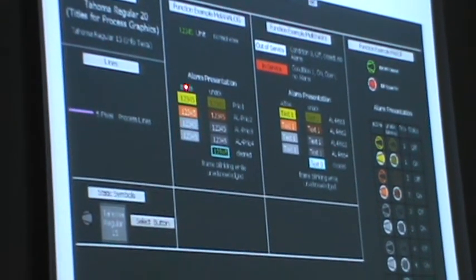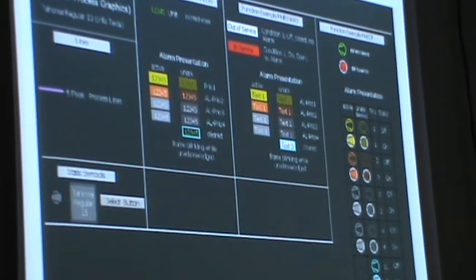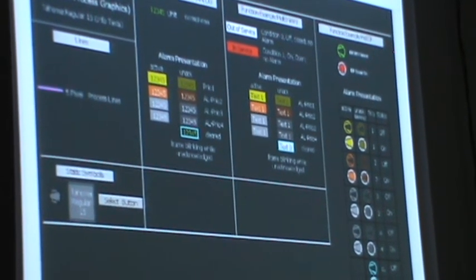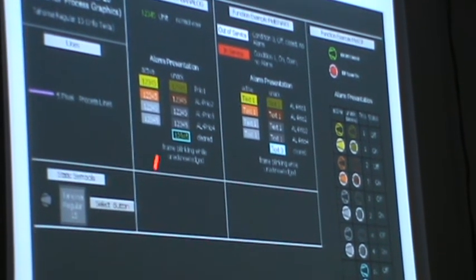And we have different priorities of alarms. Alarms can be like, this is important, this is not important. So it can be like that. Some low alarm is just to alert the operator, and low-low will get the trip. So that kind of configuration. If low-low, it means it is a high priority alarm. So we show it as yellow.